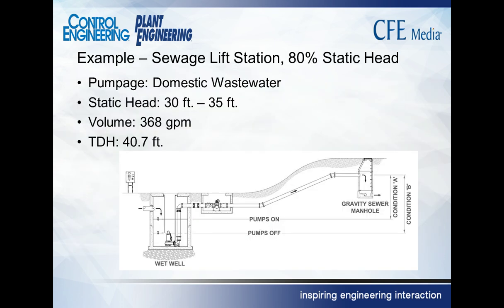And here's the other thing that happens with these types of systems. This system is set up to cycle on and off on a set of floats. So if I can turn the pump on, let it run for a while, and then turn it back off, I'll get virtually the same savings as if I had run it at a slower speed. So these types of applications don't lend themselves to energy savings from reducing the speed of the machine. They still use variable speed on sewage lift stations. There are some potential energy savings there, but nothing like what you'll find on a circulating system that has throttle control.